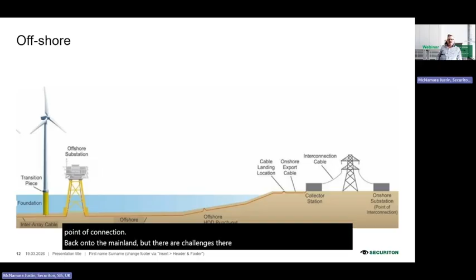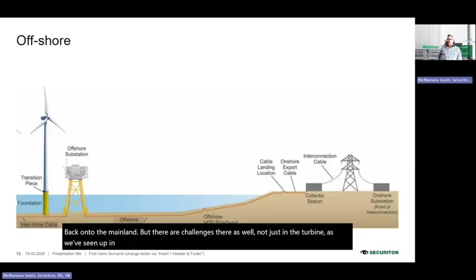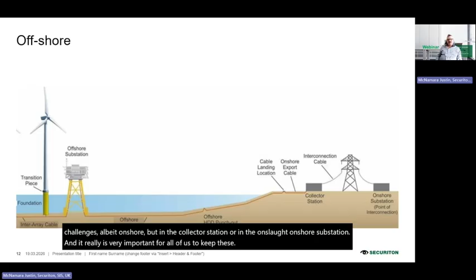There are challenges there as well, not just in the turbine, as we've seen in the nacelle and the motor, but also in the collector station or the onshore substation. It's really very important for all of us to keep these facilities, these turbines, whether on or offshore, operating, and we can do that. I would suggest strongly that aspirating smoke detection, ASD, is the right solution.